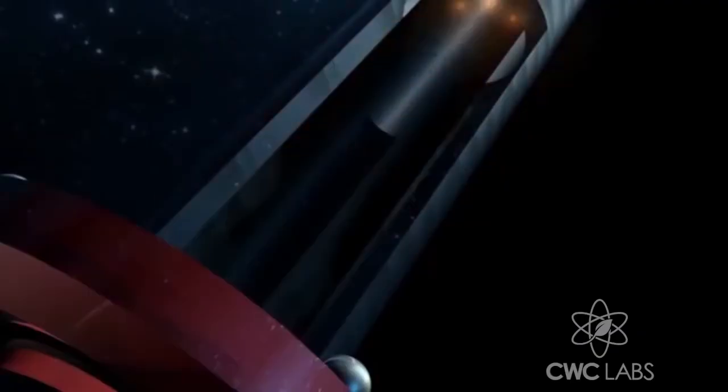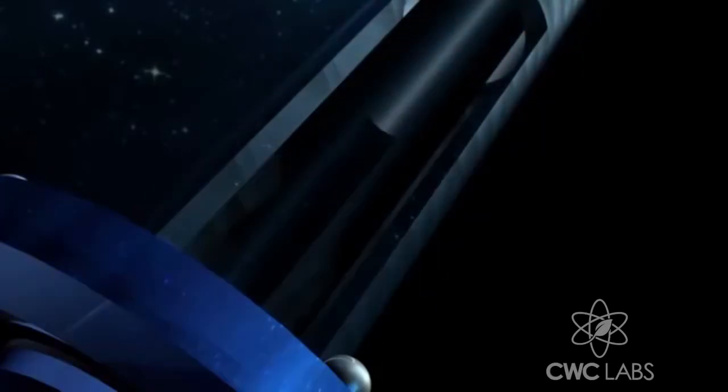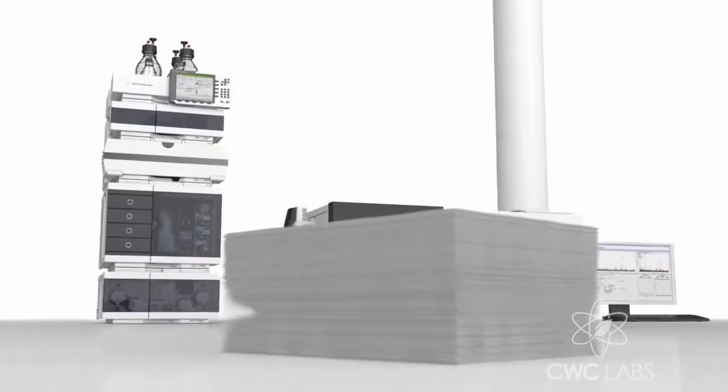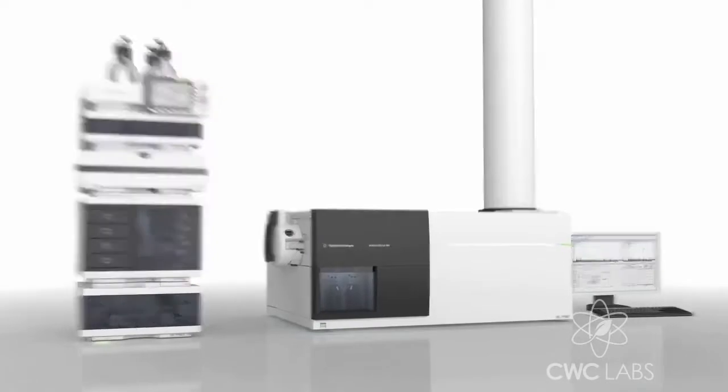From there, it goes into a mass spec system where we can look at the specific masses. We can filter out all other masses that are not 315.2319. And we can do so at very, very high resolution, as low as 3 parts per million, sometimes 5 parts per million. And that's extraordinary, because most even single quad mass spec systems don't have that kind of resolution. We have extraordinary resolution with the Agilent time of flight system, and that enables us to very accurately pinpoint the mass that we're looking for.